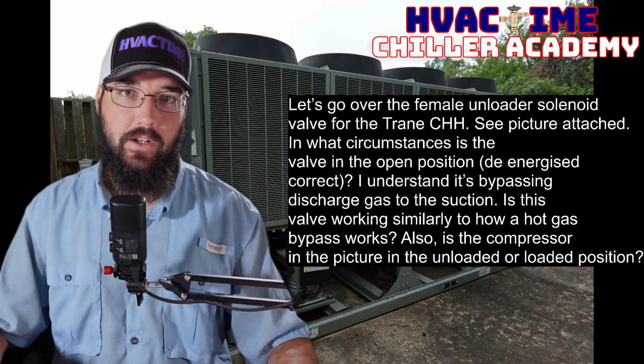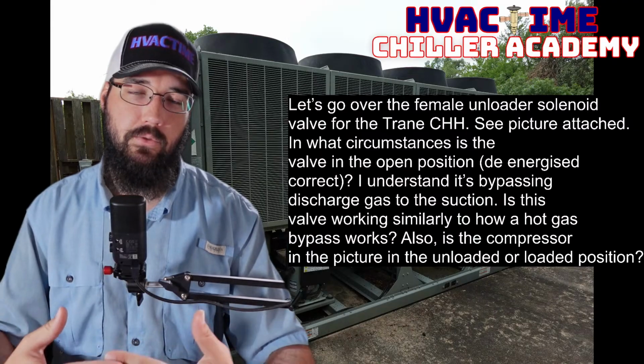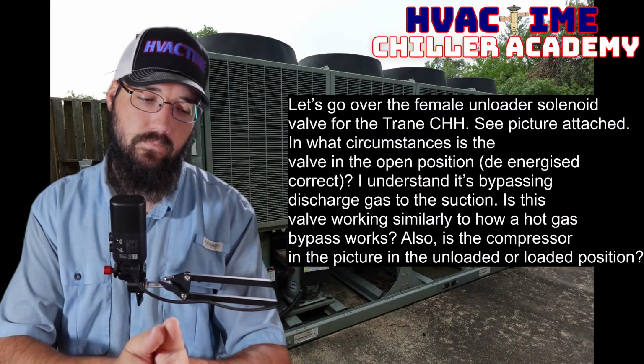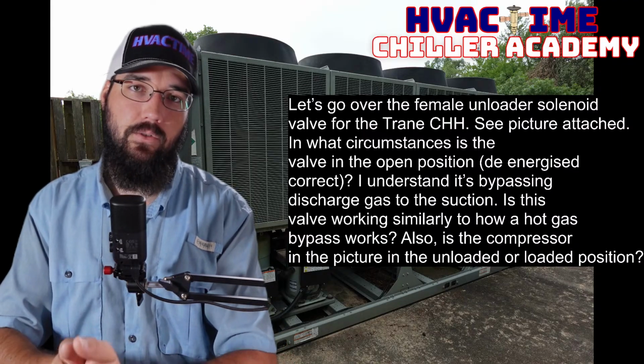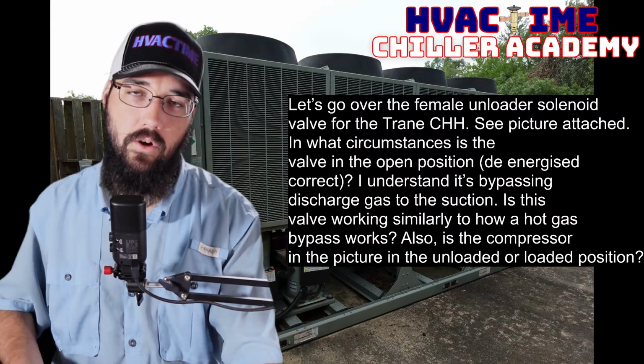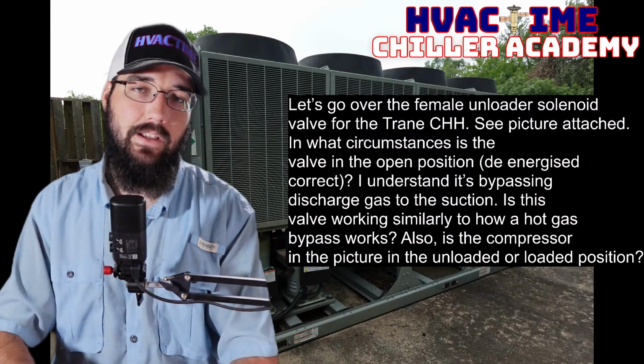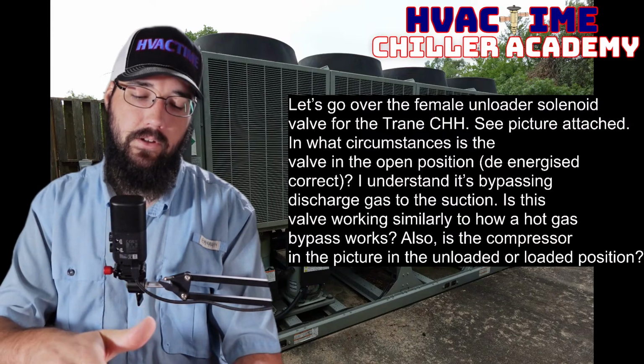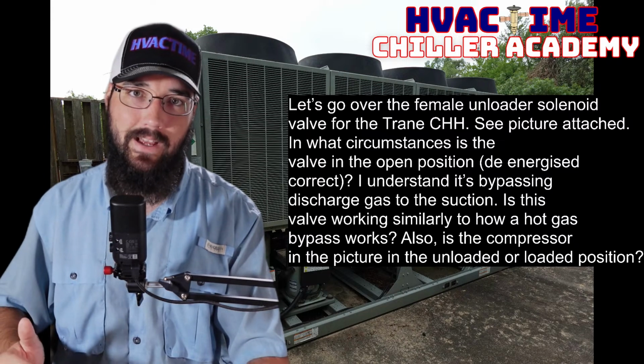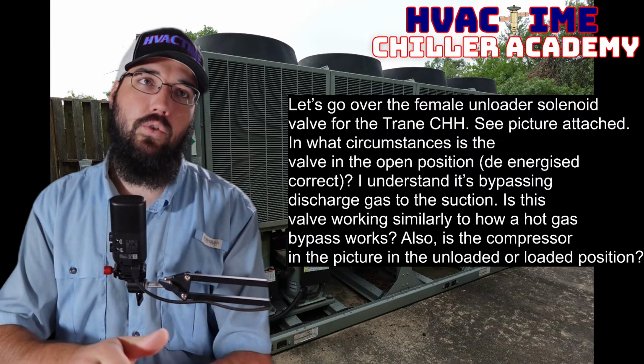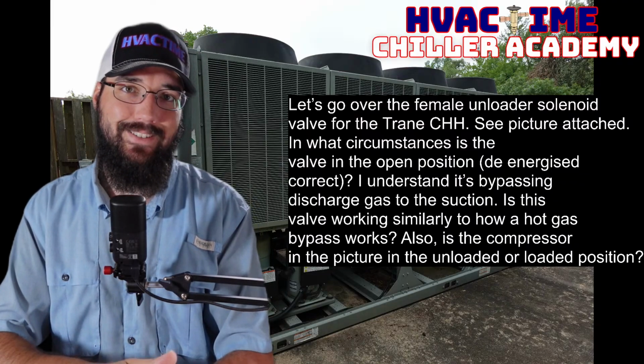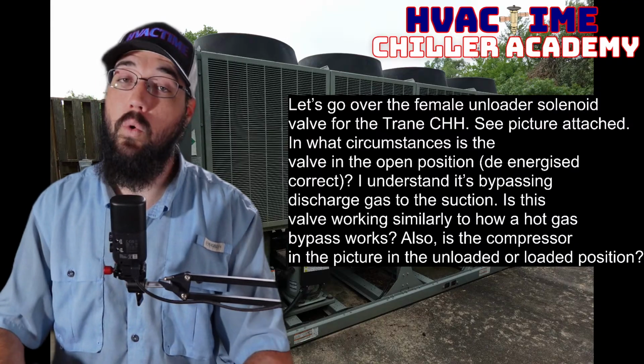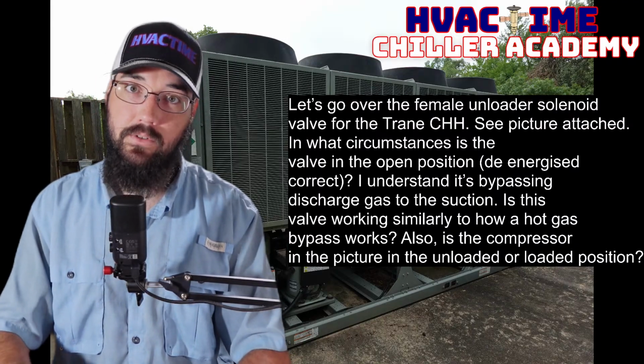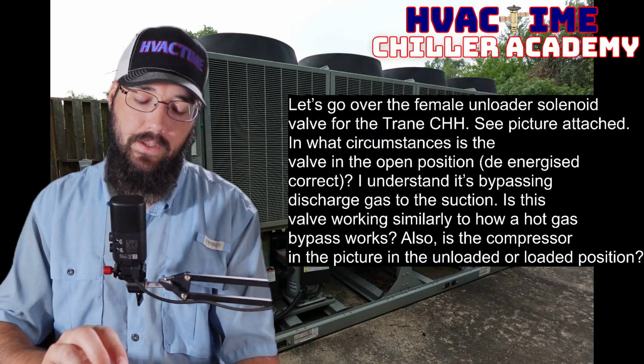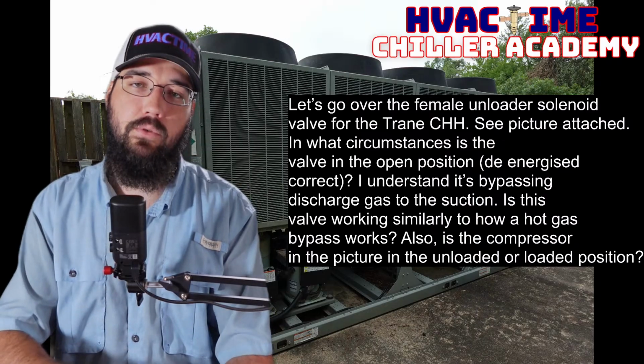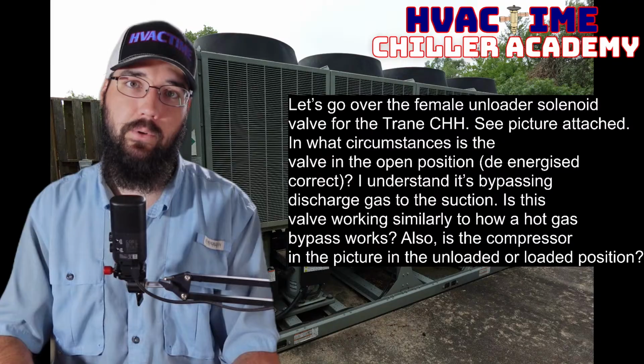So with a regular flooded, it's the other way around, where the refrigerant would be on the shell side, water in the tubes. These chillers do a pump down cycle at shutdown of the compressor. That is drawing all of the liquid refrigerant, and the EXV will fully close. So it'll completely close down, isolate the evaporator, and pump it down. That is the shutdown cycle for these. So what'll happen is when that female unloader is either stuck, not working, or is energized when it's not supposed to be, which does happen, the evaporator will pull into a low suction pressure pretty quickly.